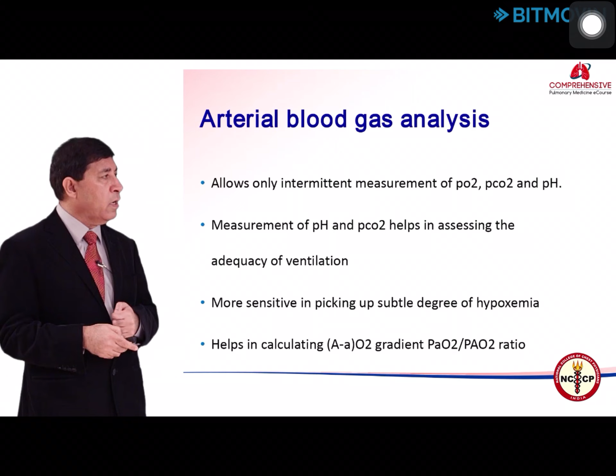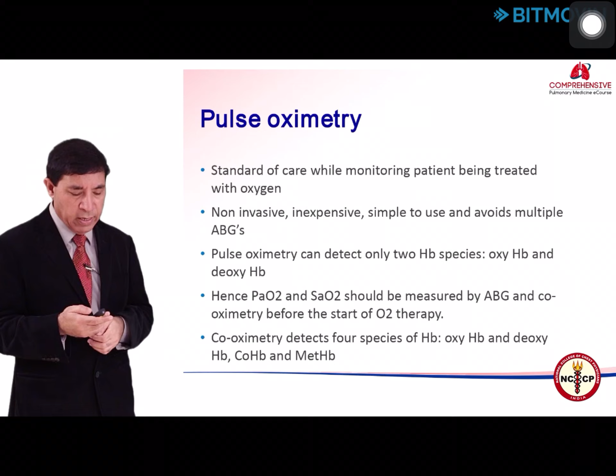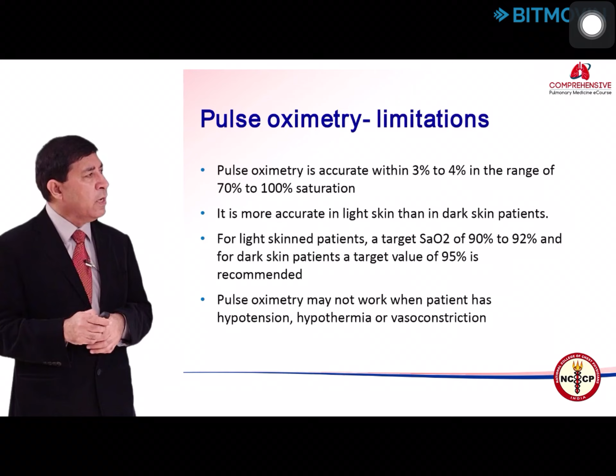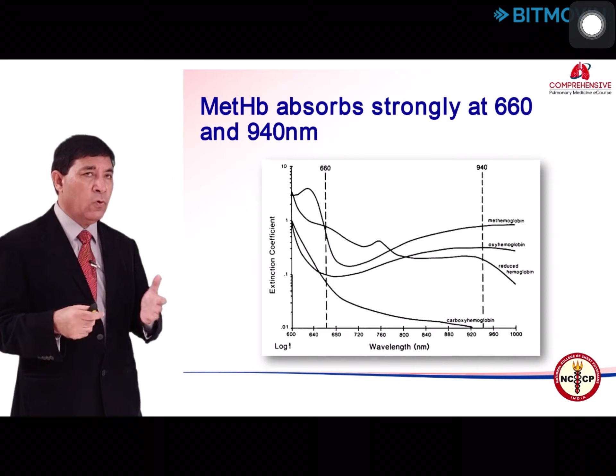So the most important way of monitoring oxygenation of your patient is the use of pulse oximetry, and it gives you continuous monitoring of the oxygen saturation. The disadvantage of pulse oximetry is that it does not give you anything about dyshemoglobins. So it will give you falsely high values if the patient has high levels of methemoglobin or carboxyhemoglobin. Most of the pulse oximeters which we use measure only two spectrums, so they will only measure either oxyhemoglobin or deoxyhemoglobin. It is disadvantageous that way, and it may also not be very useful in patients who are hypotensive and patients with shock. The values may not be very effective, and also in patients who have low values, less than 70%.